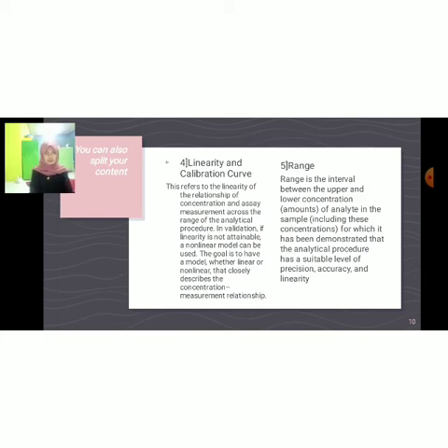And the fifth is range. Range is the interval between the upper and lower concentrations or amounts of analyte in the sample, including the concentrations for which it has been demonstrated that the analytical procedure has a suitable level of precision, accuracy, and linearity.